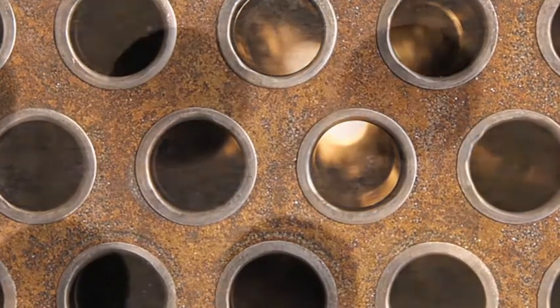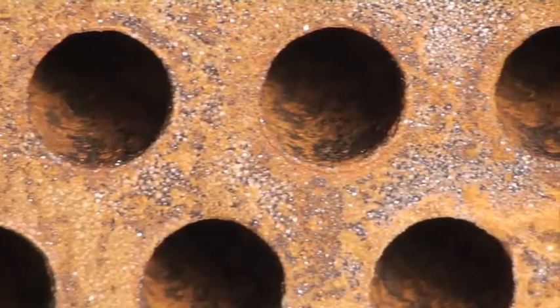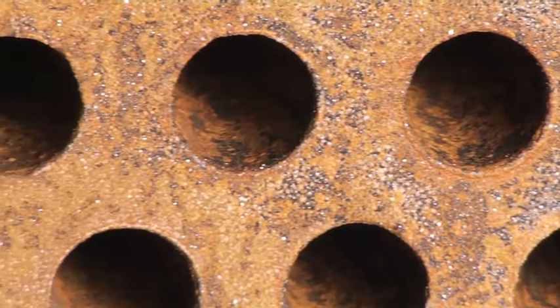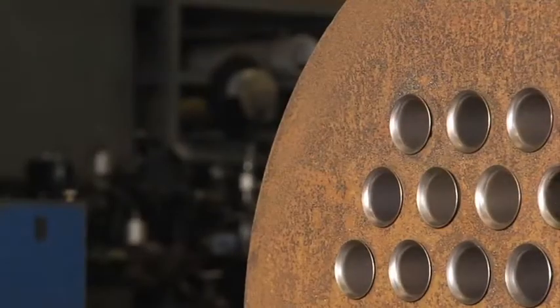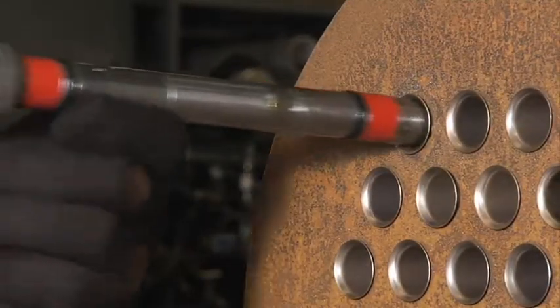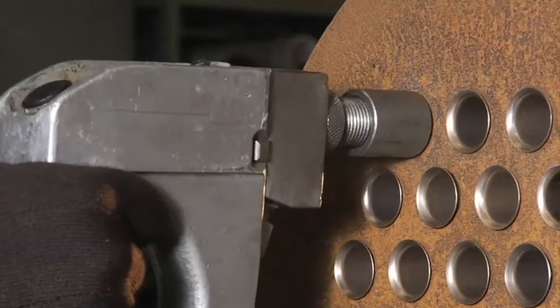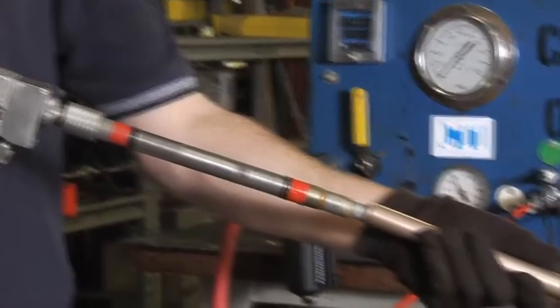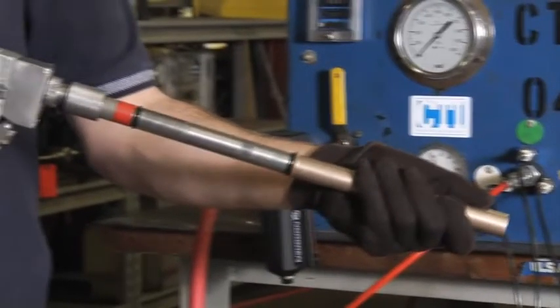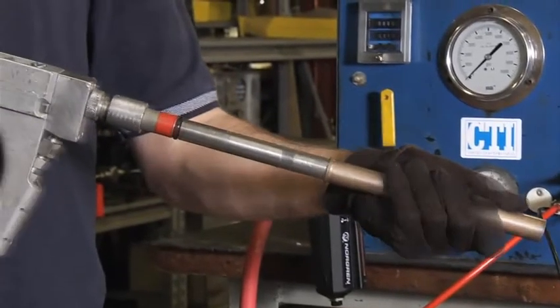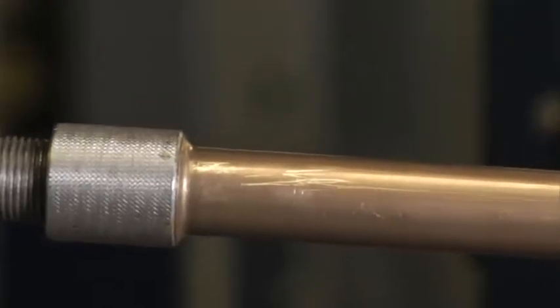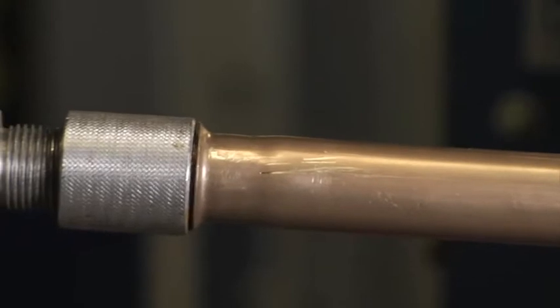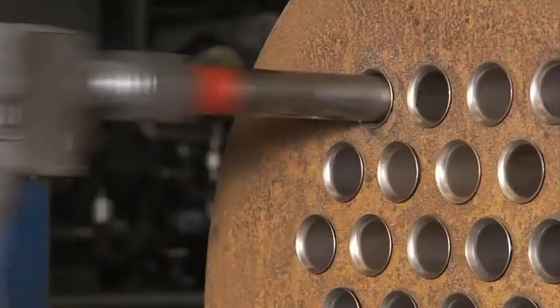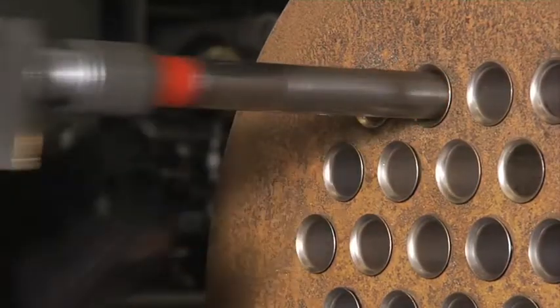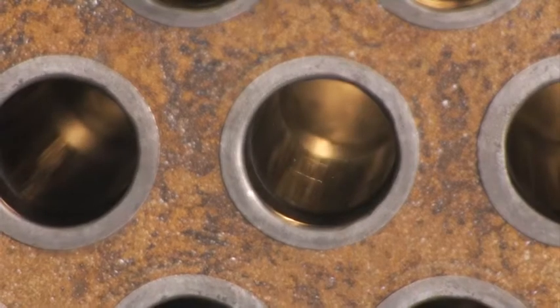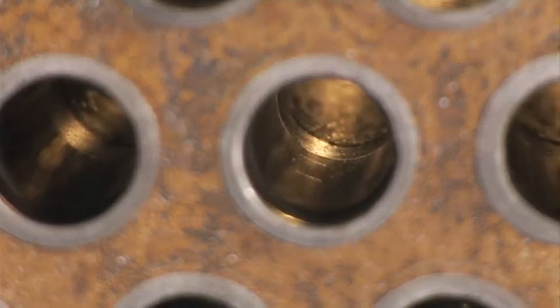In the case of high-pressure units, or those containing an online tube cleaning system, shields can be expanded their full length by use of CTI's hybrid expansion technique. Once calibrated, the mandrel is inserted into the shield and the hydraulic pump engaged, expanding the shield into the existing tube. This method works in conjunction with the mechanical expansion at each end, which is accomplished on all shield installations.